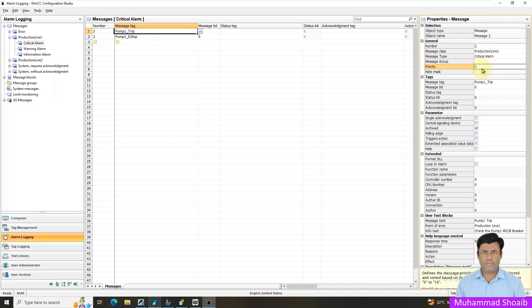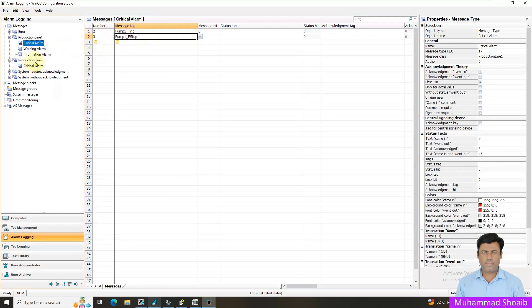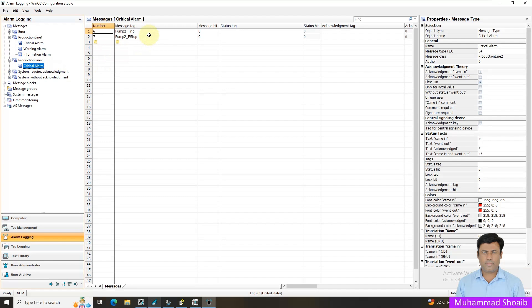We will now assign priority levels based on criticality. For me, the most critical signal is a trip — so I assign priority 1. Similarly, emergency stop gets priority 2, to differentiate that it is also critical but slightly less so than priority 1. In production line two, pump two trip also gets priority level 1 and emergency stop gets priority level 2.